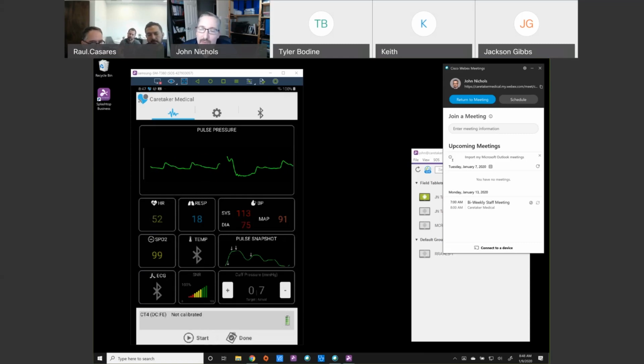So the manufacturer of the Bluetooth pulse ox obviously wanted to save money. So they only put 2 digits on their display instead of 3. So when a patient's at 100 on that finger clip unit, it'll actually show 99. But on our app, we'll show 100. So it's only when they're reading 100 and displaying 99 where there'll be a disagreement between what we're showing you and what it's showing you. Okay? We had one customer bring that up, and it was like a major problem, and we determined that that's the reason why they just didn't put a 3rd digit on their display.